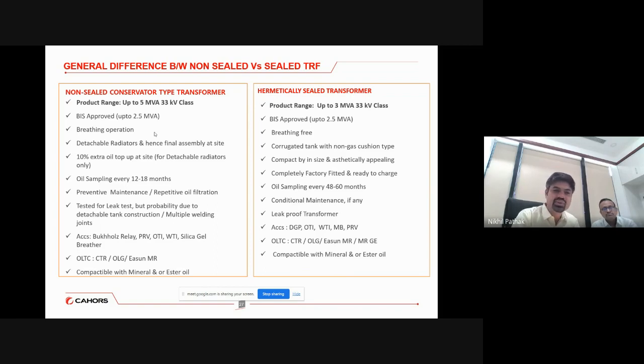Secondly, on the left-hand side you can see a non-sealed transformer comes with detachable radiators. So final assembly of the transformer has to be done at site. These need some 1 or 2 days for the installation, as in case of the 2.5 MVA or 3 MVA transformer. However, the corrugated transformer comes with a complete factory-fitted approach. So it does not need any exclusive support for the installation. Only the general SOPs are to be followed: the termination, control wiring, earthing, all those things are done. Then the transformer gets ready for charge.